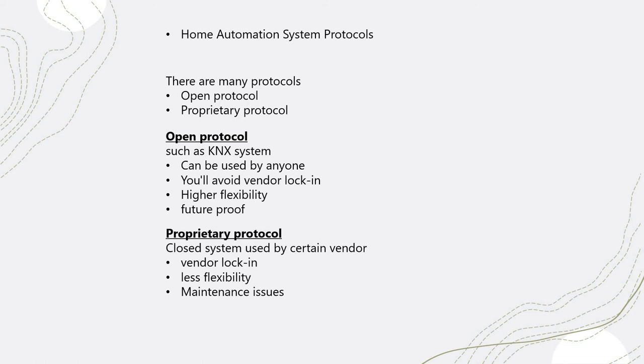Closed protocols are used for certain vendors only. You have a lack of choice — you can only select products manufactured by a specific company and cannot mix devices from different manufacturers. This creates less flexibility and more hassle for maintenance, because only authorized installers or integrators certified by that manufacturer can perform maintenance. With open protocols, any certified engineer who knows the system can solve your problem without too many hassles on the maintenance side.